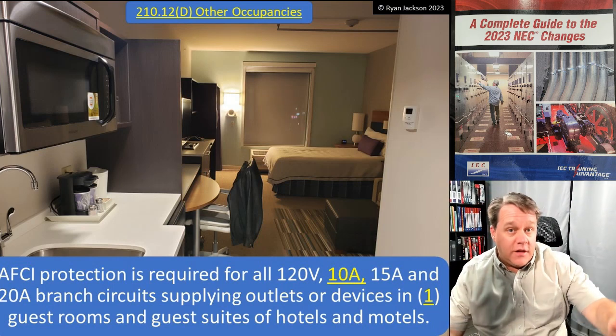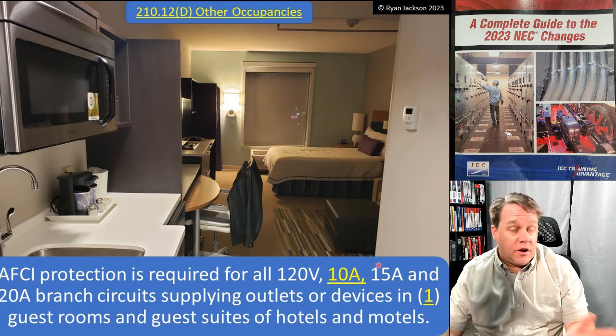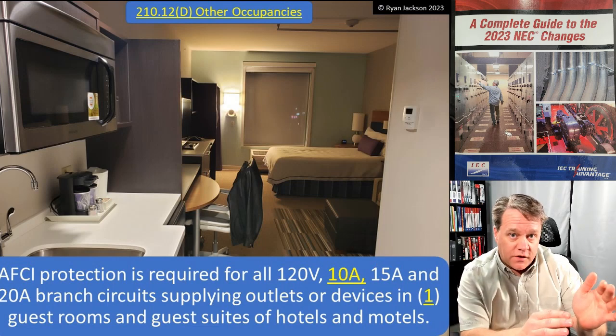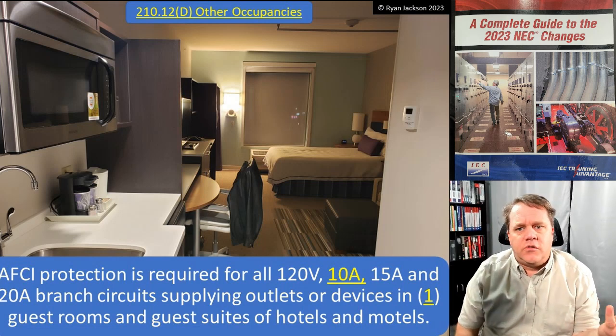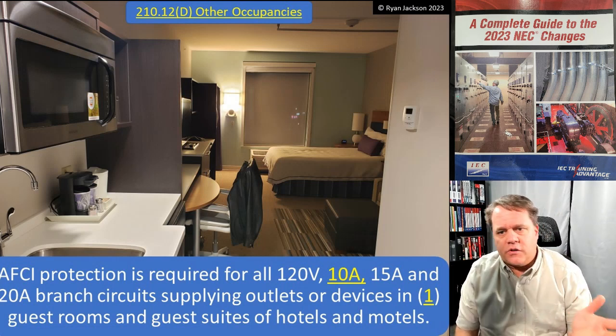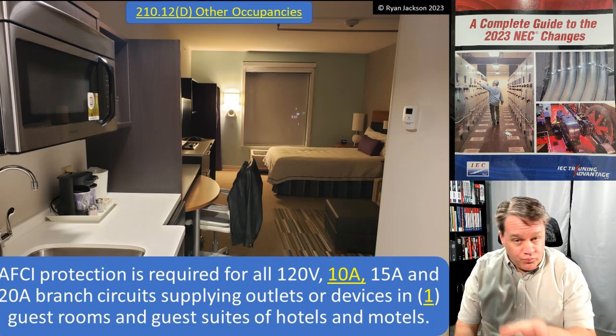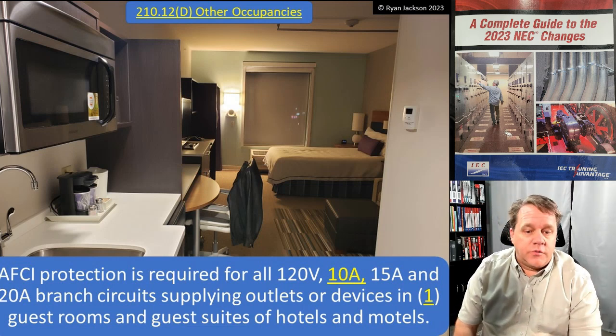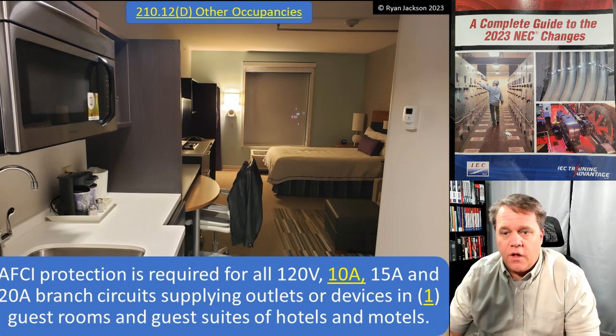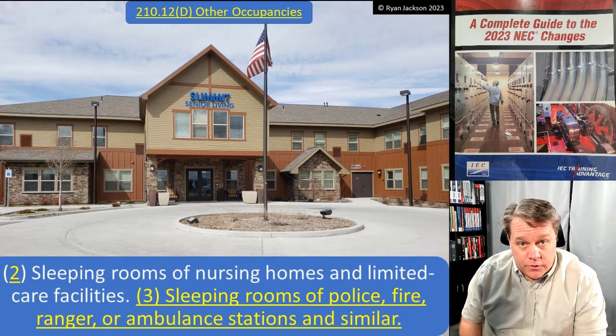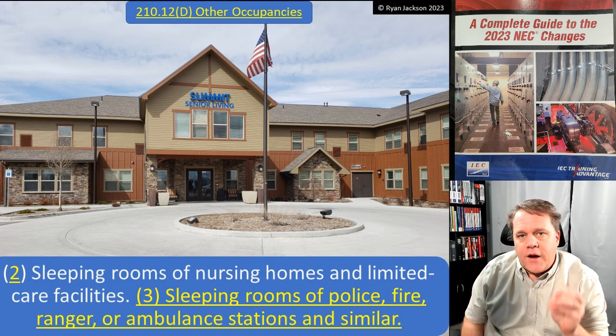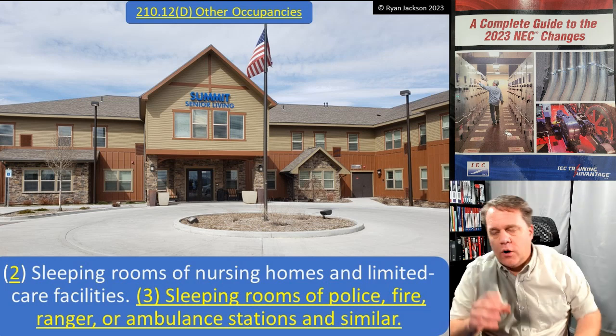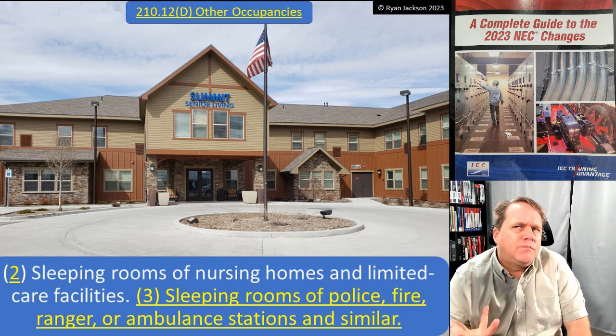So what changed? Not much yet. Section 210.12 is organized with part A covering types of AFCI devices, B for dwelling units, C for dormitories, and D for hotels and motels, and then other occupancies including guest rooms and guest suites of hotels and motels, sleeping rooms of nursing homes and limited care facilities, and sleeping rooms of police, fire, ranger, and ambulance stations and similar occupancies.